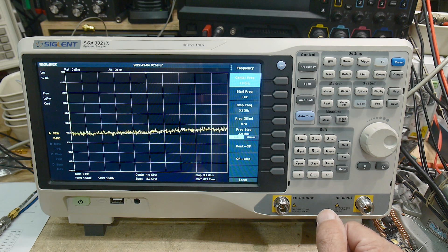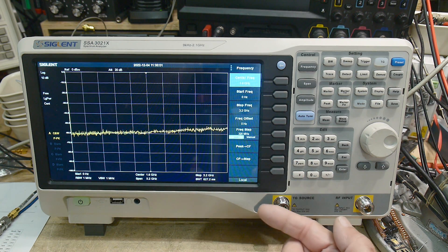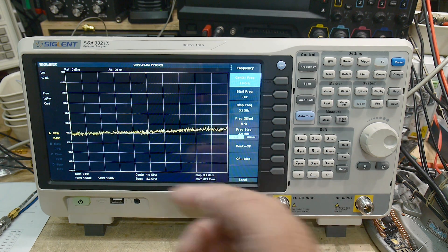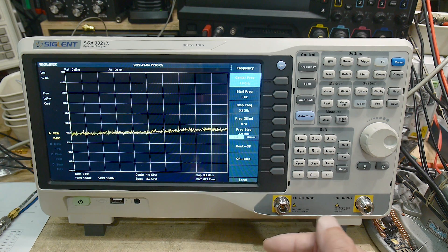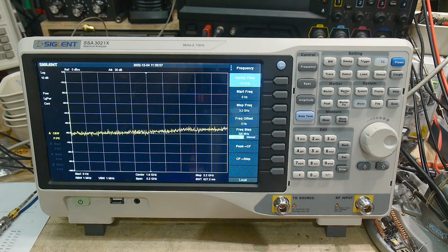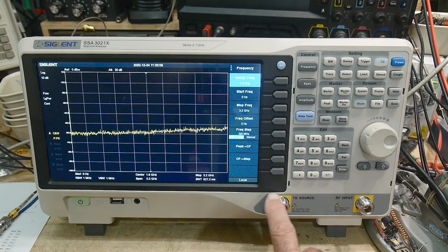There are some extra things that this instrument has that the old guys didn't have. There is two modes this has. It has spectrum analyzer mode and it has return loss mode, so you actually can display the VSWR.